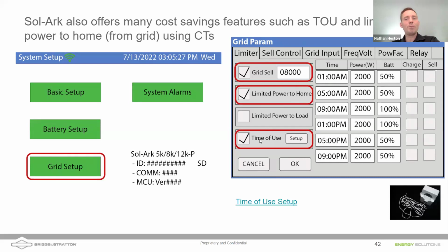You can also do time of use, and you are allowed to set up different times where you're discharging your batteries at rates that you can program in during certain windows of time. So I can program different powers. I've got them all set to 2000 right here, but you can program in different rates at different times of the day.